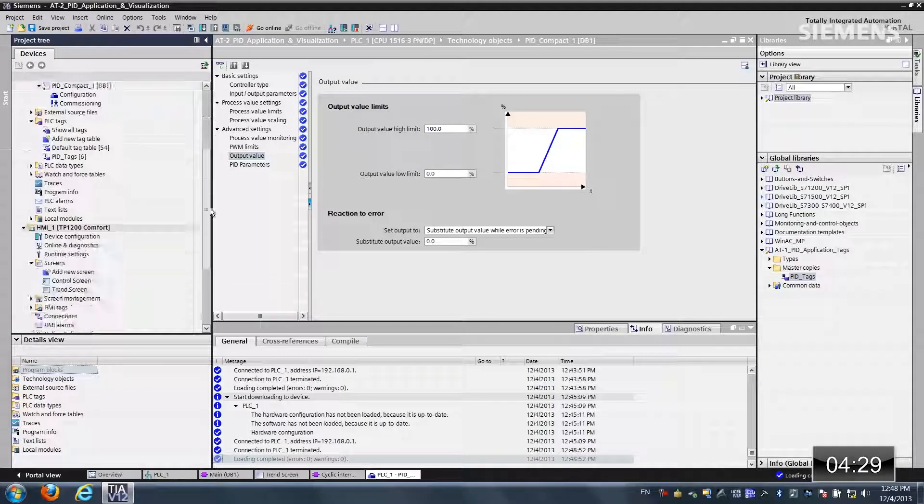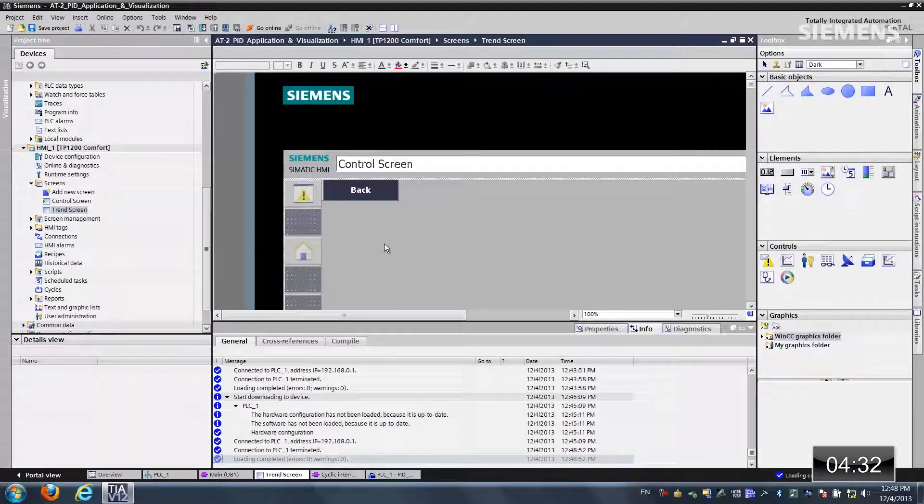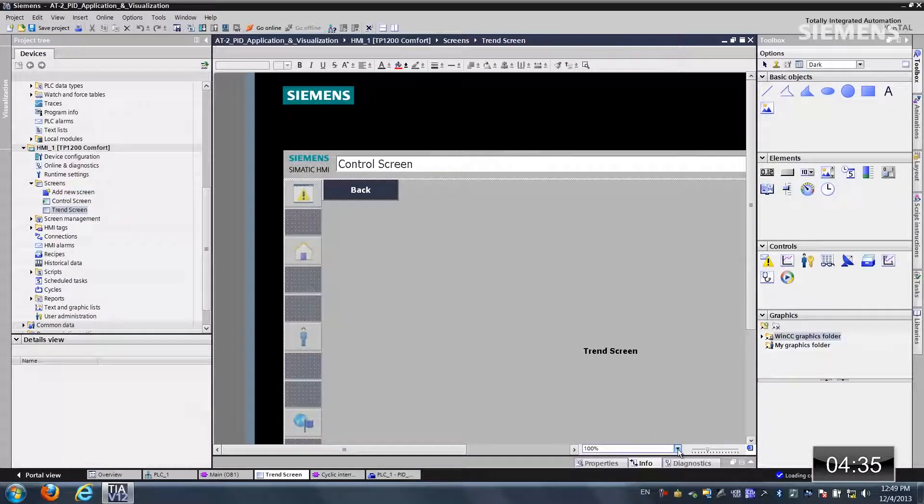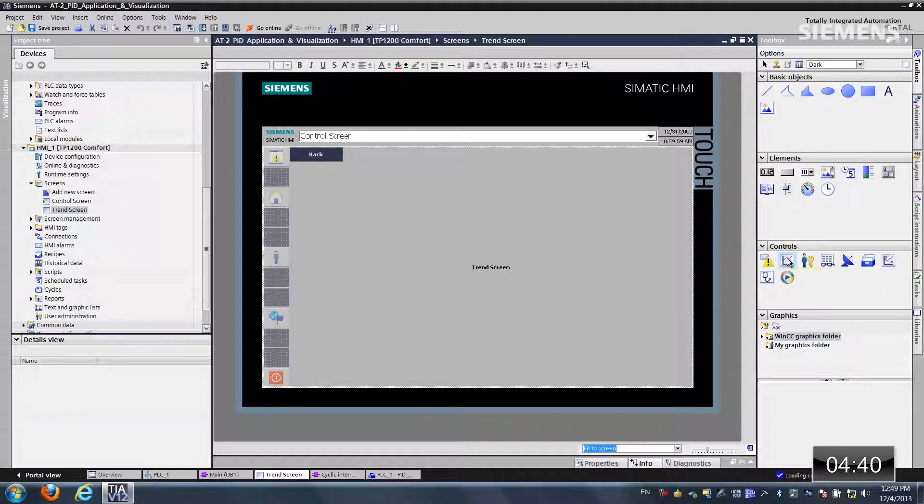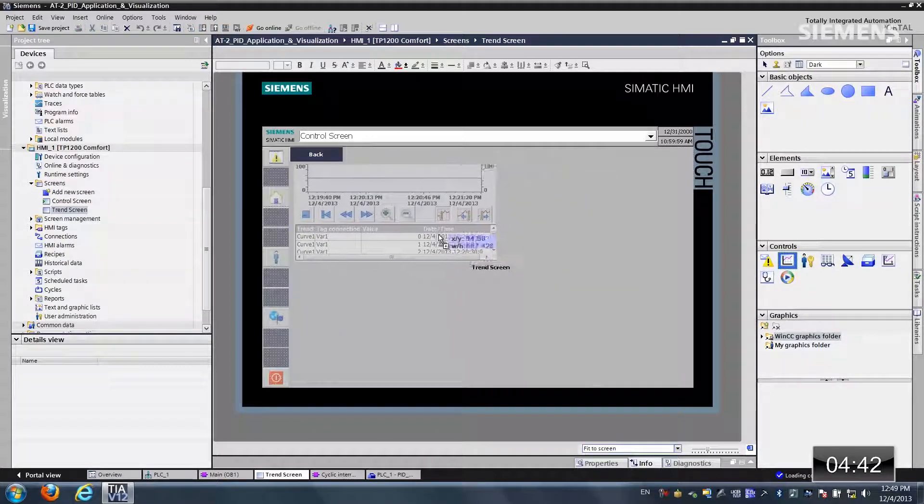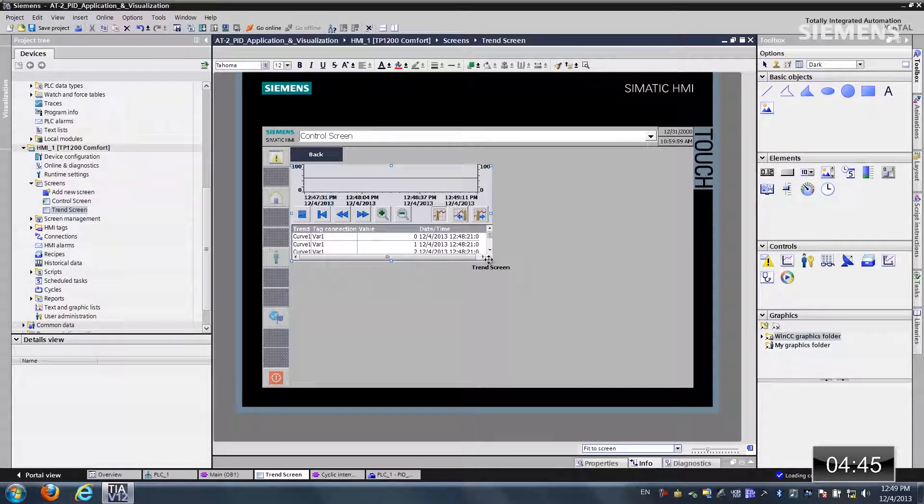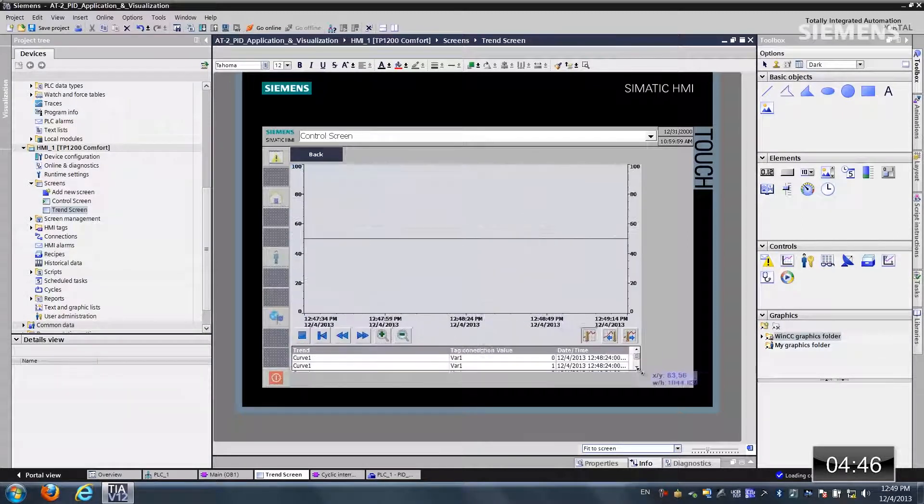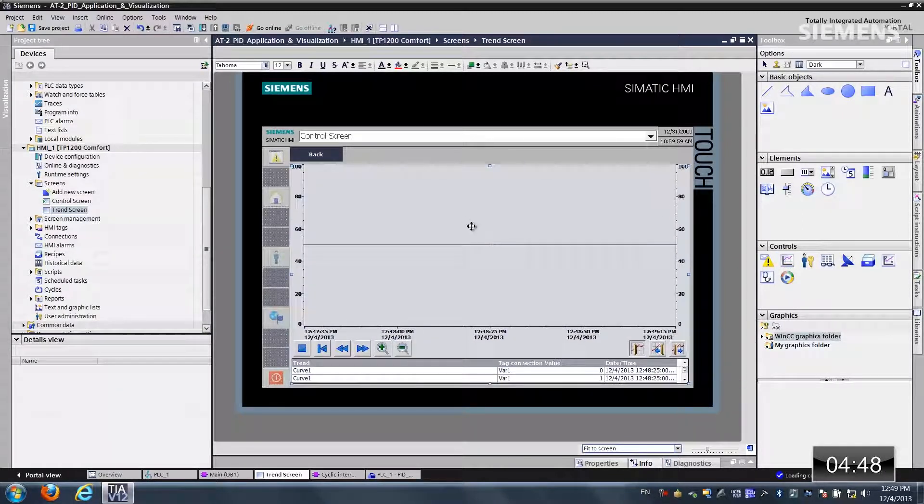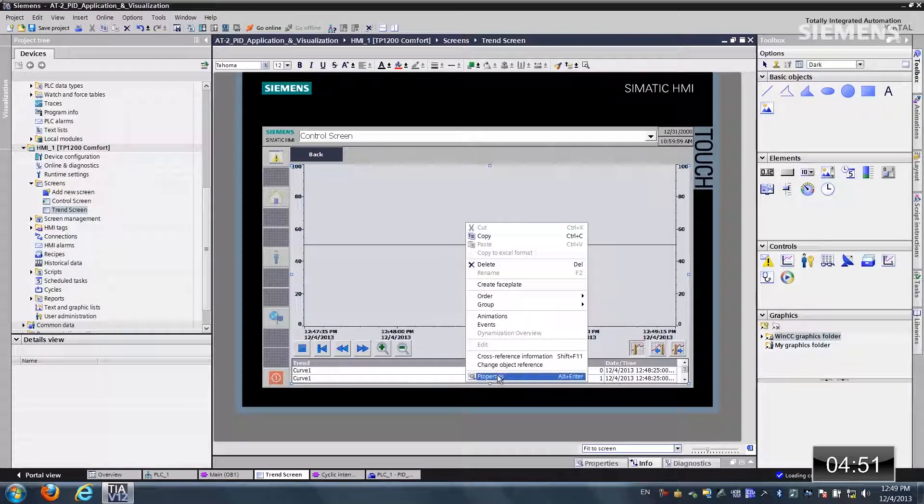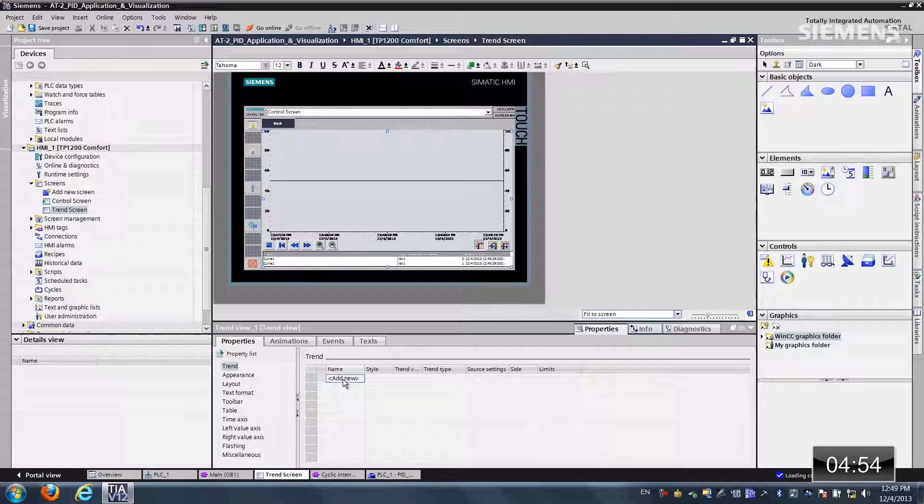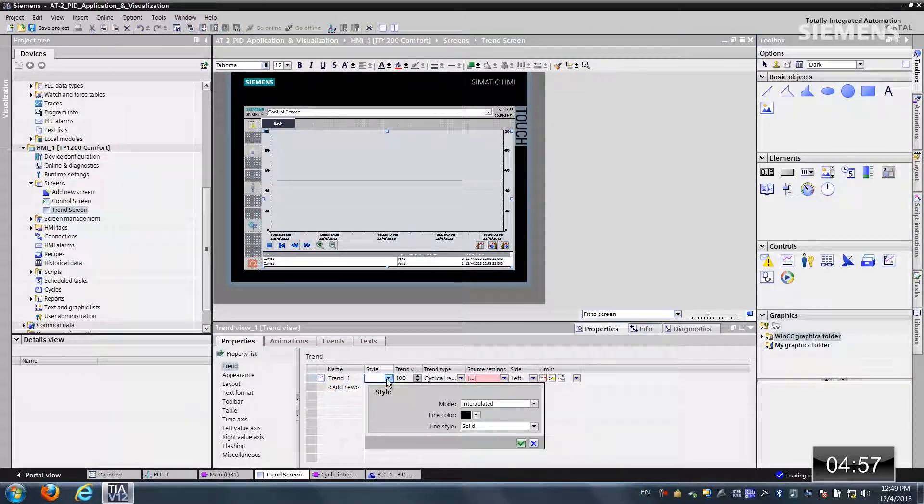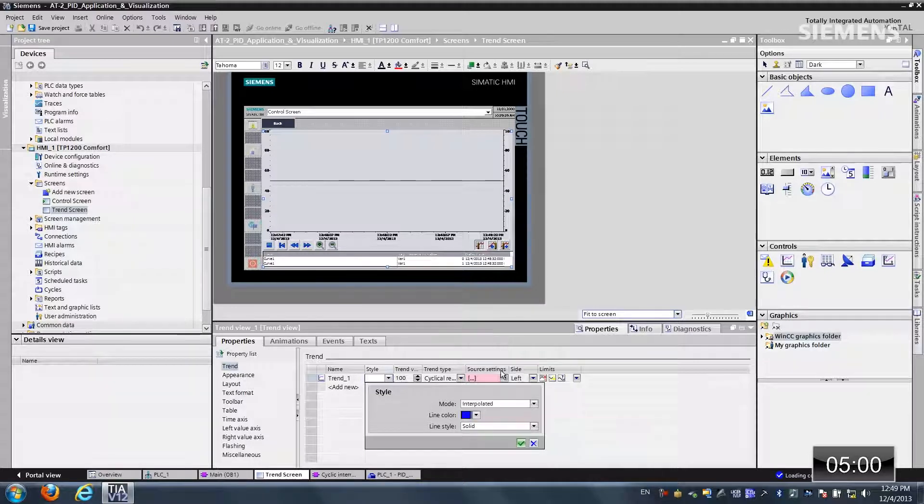The next step is visualization. What I would like to do is come over to a 12 inch comfort panel. And let's double click on the trend screen. Let's give complete focus to it. Click on fit to screen. Now at this point, I want to drag and drop this control icon called the trend view. This is an ActiveX control. Let me resize and refit him. Now let me actually give focus to him. Right-click and choose properties. Let me add the first variable in. And let's change an attribute. Let's change it to a blue line instead of black.